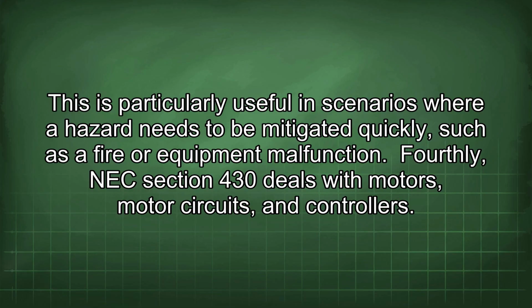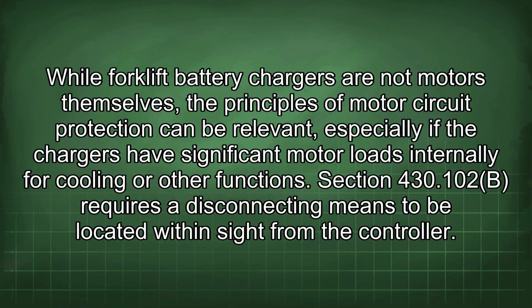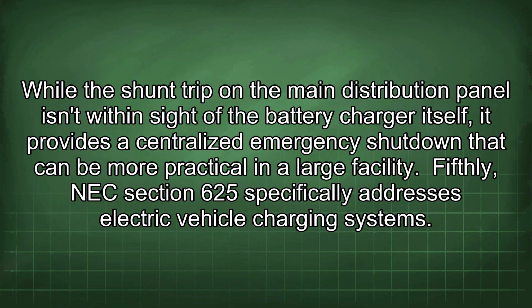Fourthly, NEC Section 430 deals with motors, motor circuits, and controllers. While forklift battery chargers are not motors themselves, the principles of motor circuit protection can be relevant, especially if the chargers have significant motor loads internally for cooling or other functions. Section 430.102(B) requires a disconnecting means to be located within sight from the controller. While the shunt trip on the main distribution panel isn't within sight of the battery charger itself, it provides a centralized emergency shutdown that can be more practical in a large facility.